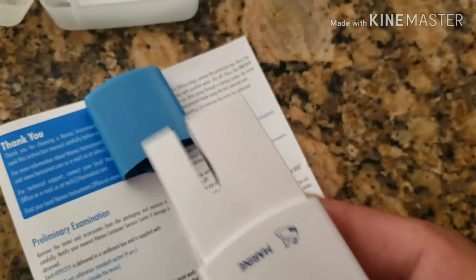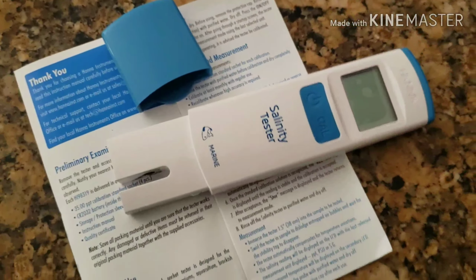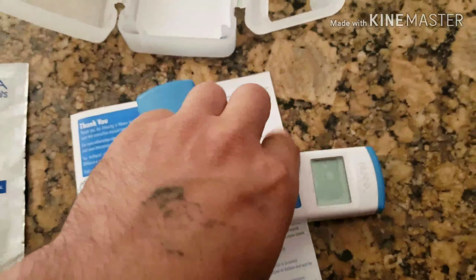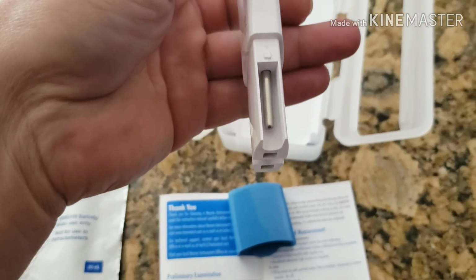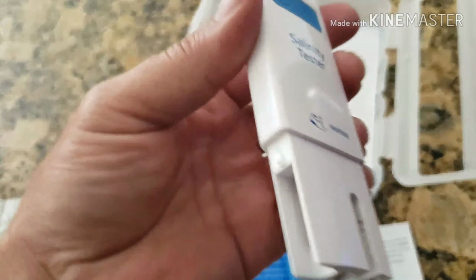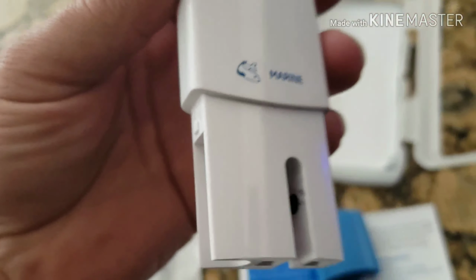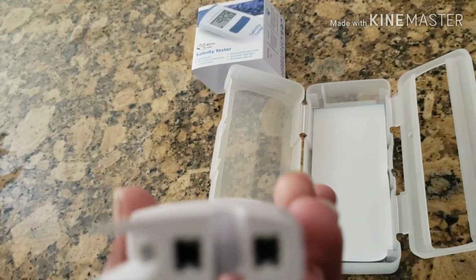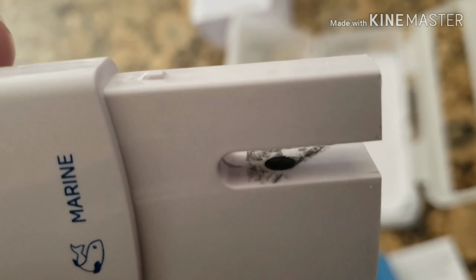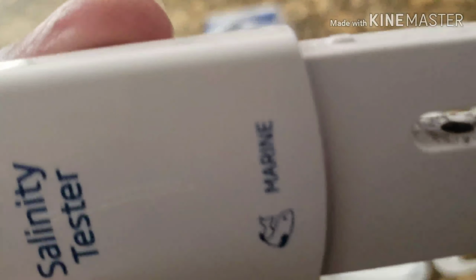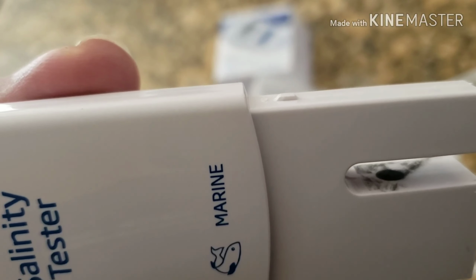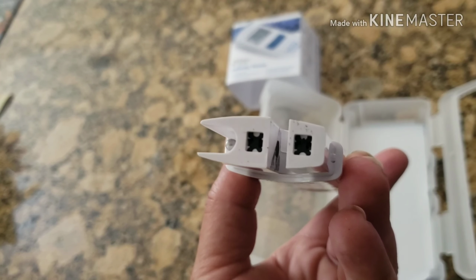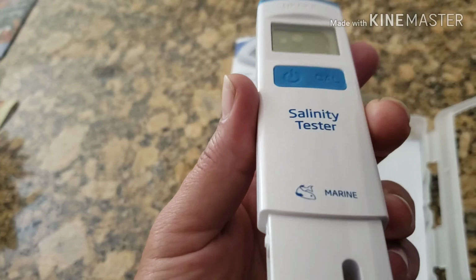So what they're talking about here, I've already calibrated this and cleaned it off, but you need to rinse the temperature probe on the side there, as well as the little graphite probe sensors on the side there. It does look dirty, but I assure you I have rinsed this off and wiped it out with a paper towel. I guess I could probably get in there with a Q-tip and get some of that graphite dust off a little easier. It's got two little slots in the bottom where the water picks up.